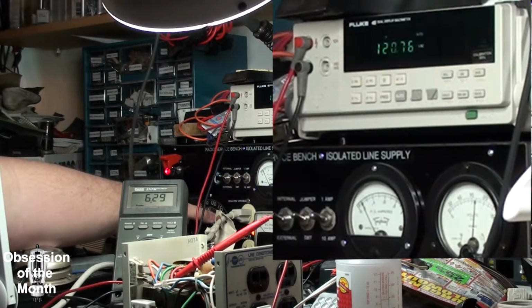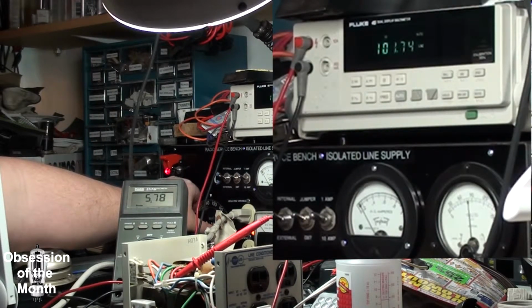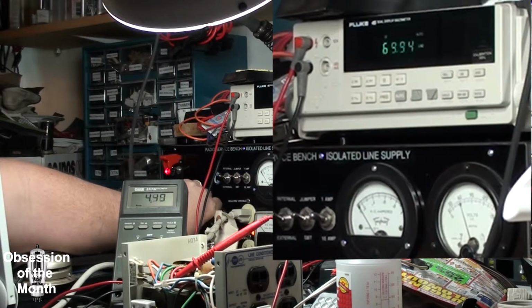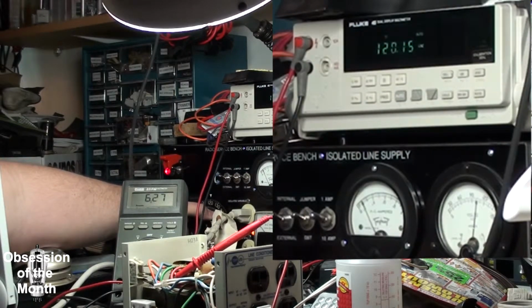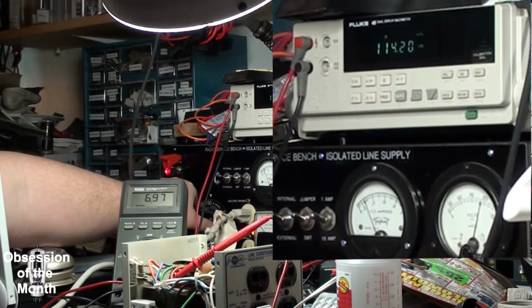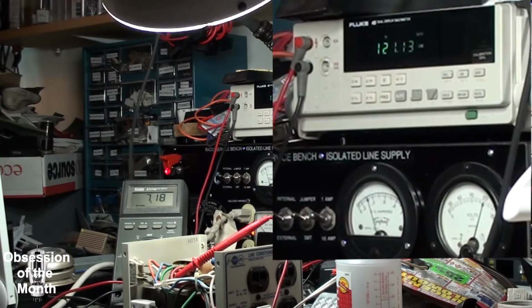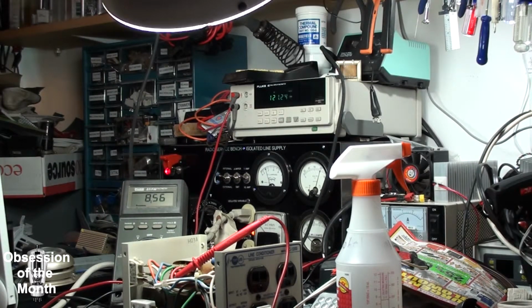Now I'm going to drop the voltage down again, and I think this is the limit. Yeah, it can't do any more. So we're going to go back up. It's kicked in again, and that's as high as my variac will go. It's supposed to go to 135, but due to the way this thing is built, it only puts out a maximum of about 120, 121 volts.